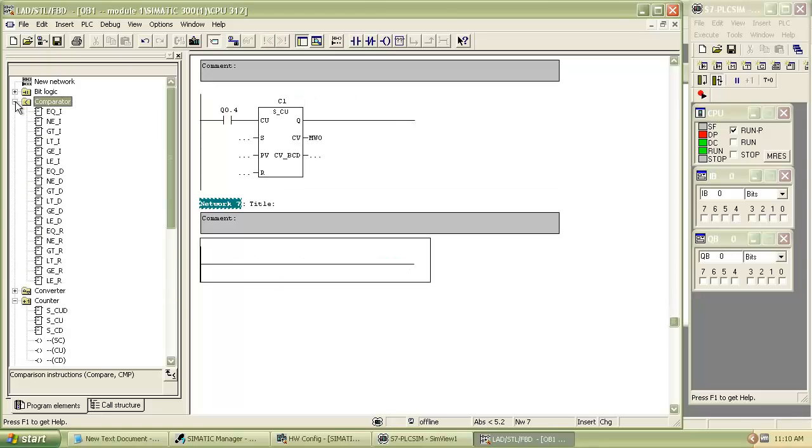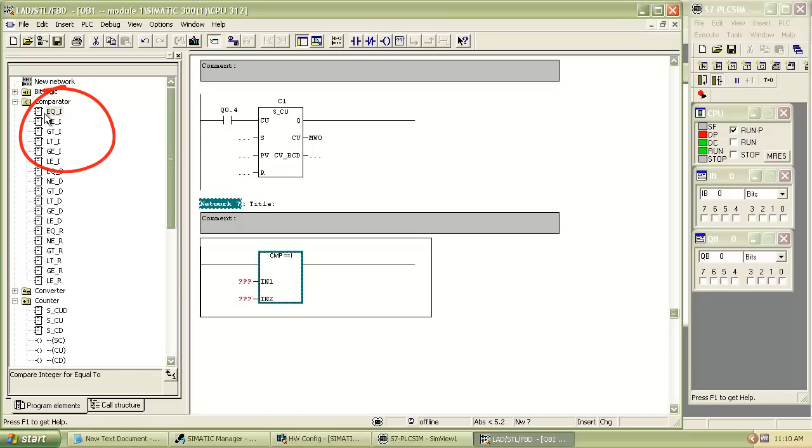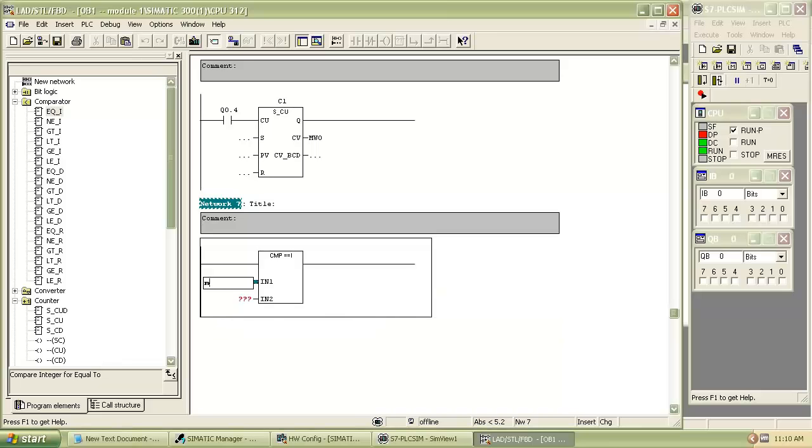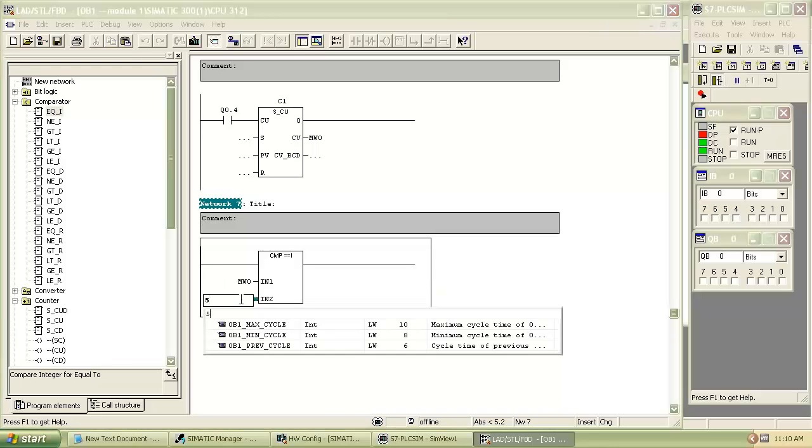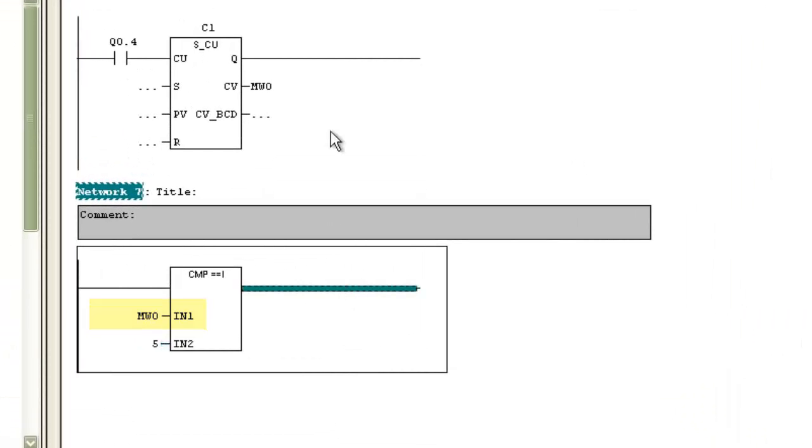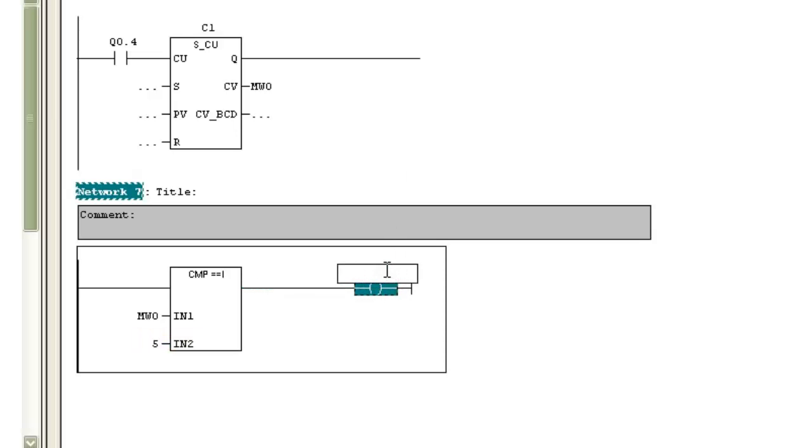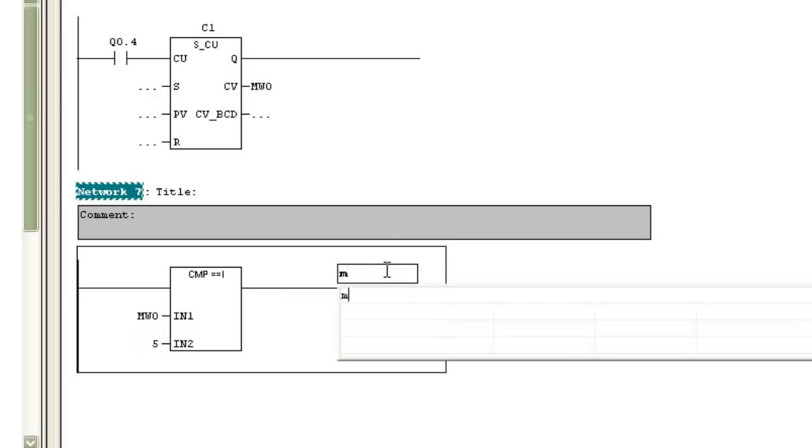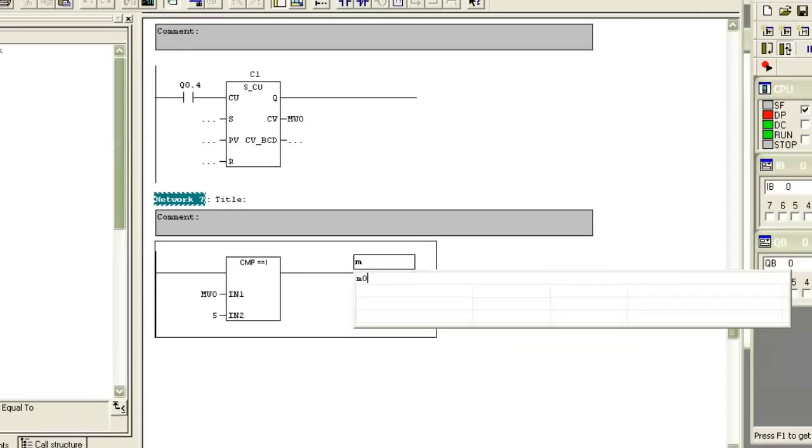Insert the comparator from program elements under the comparator tab. Select equal value comparator, which means when the value to be compared and given value become the same, the output will switch on. IN1 and IN2 are the two values for comparison; when these two values are equal, the output switches on.